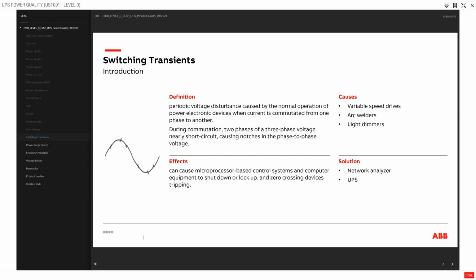Definition: periodic voltage disturbance caused by the normal operation of power electronic devices when current is commutated from one phase to another. During commutation, two phases of a three-phase voltage nearly short circuit, causing notches in the phase-to-phase voltage. Causes: variable speed drives, arc welders, light dimmers. Effects: can cause microprocessor-based control systems and computer equipment to shut down or lock up, and zero-crossing devices tripping. Solution: network analyzer. UPS.